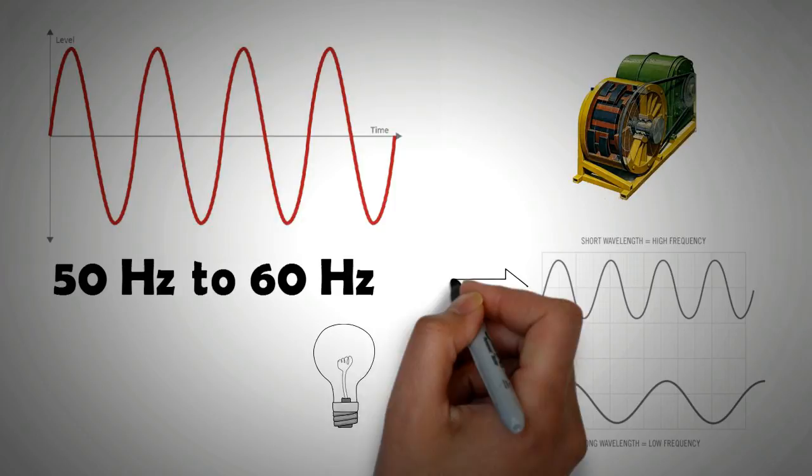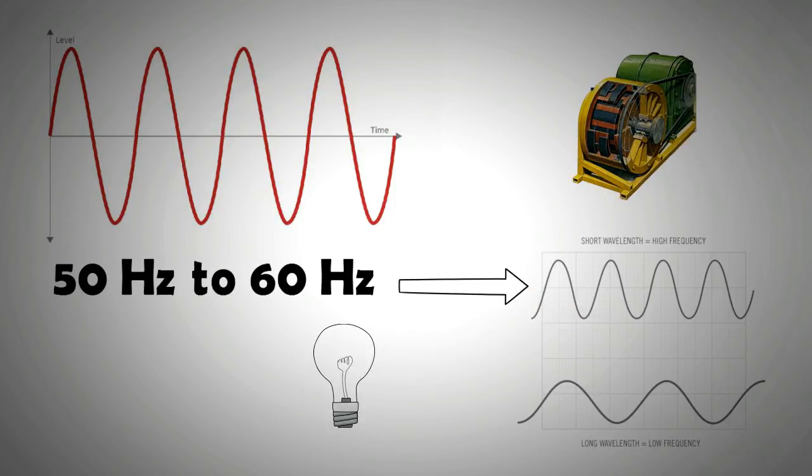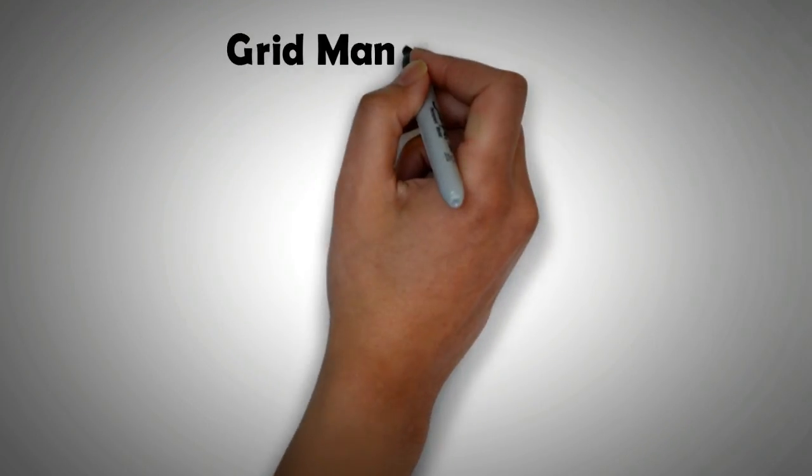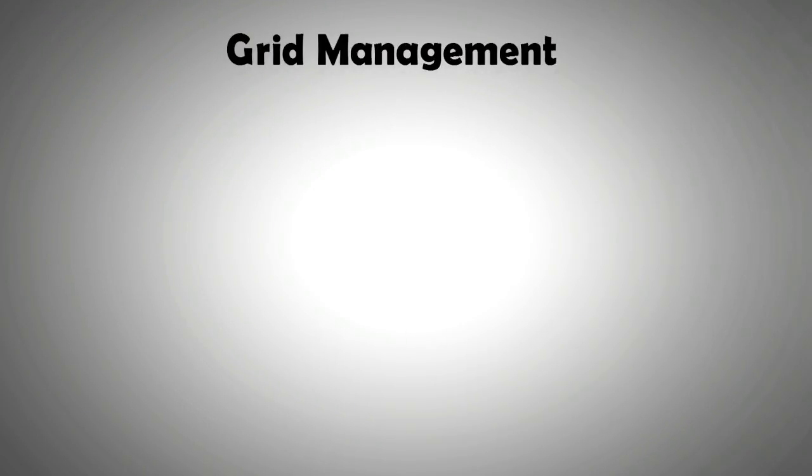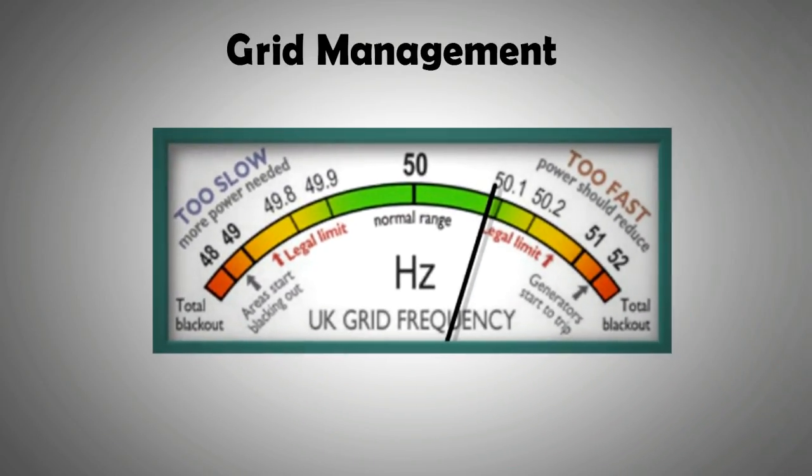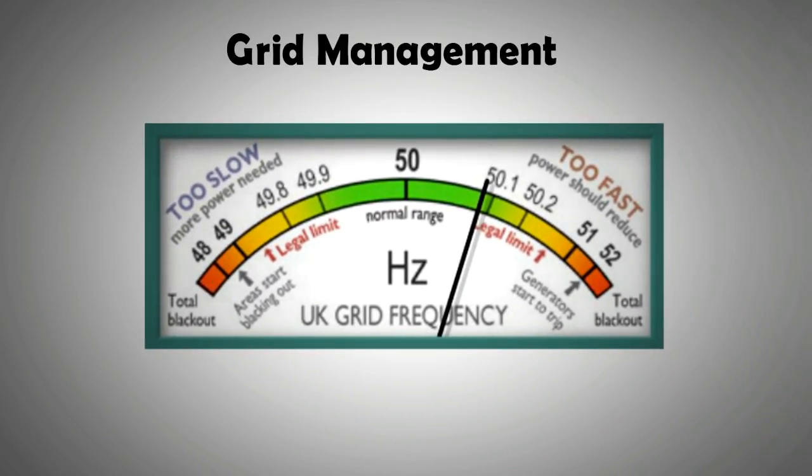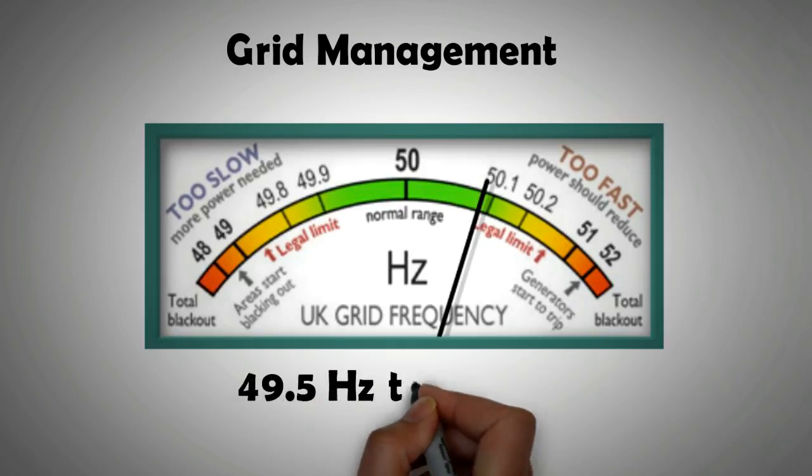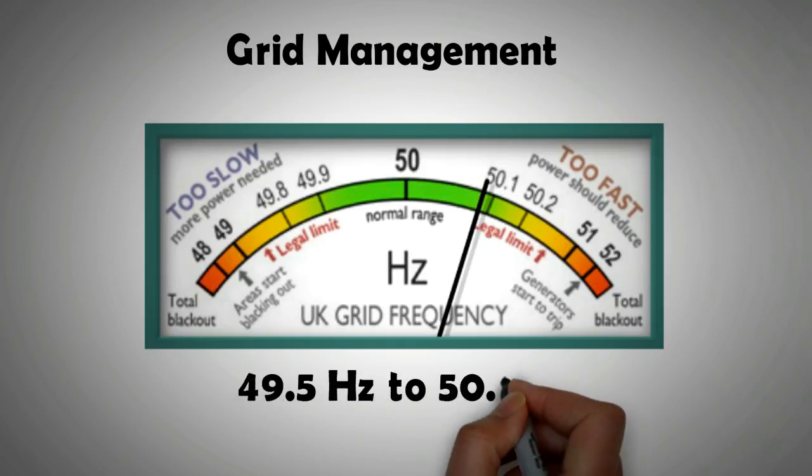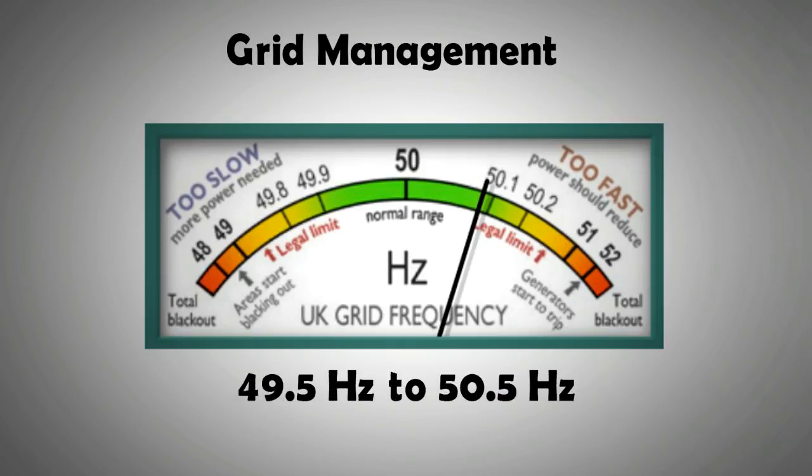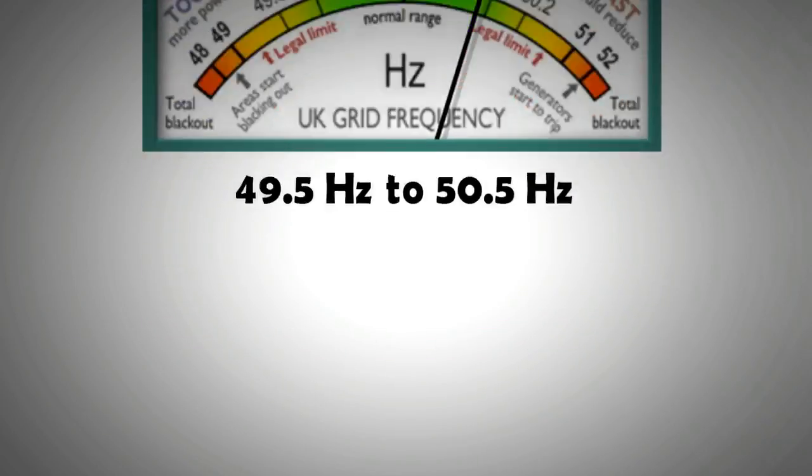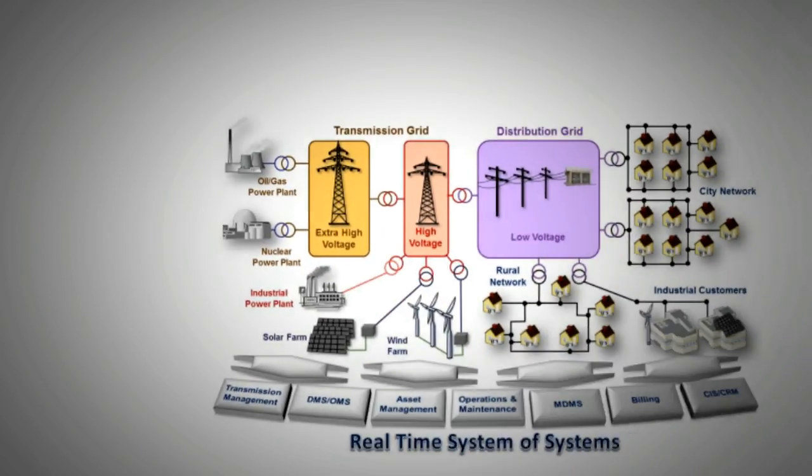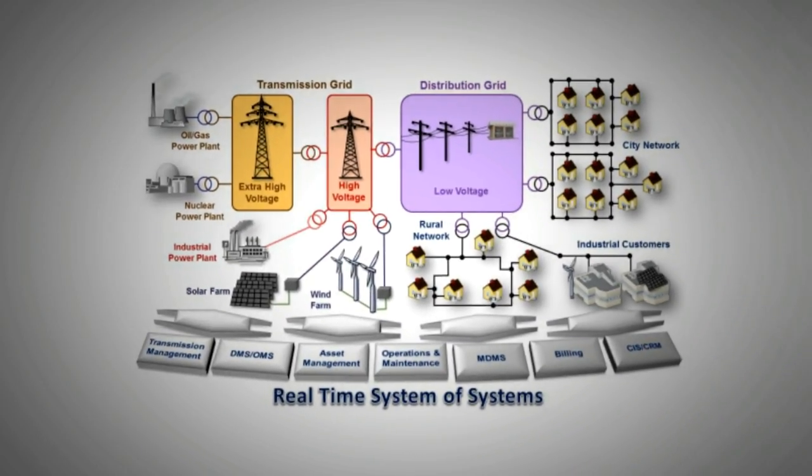Grid management companies are responsible for keeping the grid frequency within a certain range, because if the frequency of power one receives is very high or very low compared to rated power, then it can damage electrical or electronic devices. For instance, in the UK, a company called National Grid is responsible for managing the grid frequency. The range it tries to limit the frequency to is 49.5 Hertz to 50.5 Hertz.